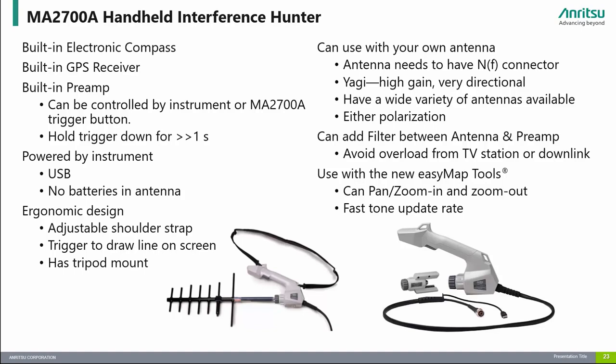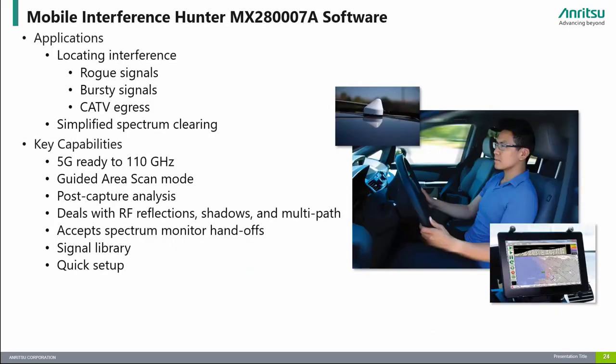The frequency range of the MA2700A is from 10 MHz to 6 GHz. Anritsu's mobile interference hunter MX280007A works with a broad array of Anritsu's handheld spectrum analyzers, providing interference hunting and spectrum clearing capability from 9 kHz to 54 GHz. The system uses proprietary interference-finding algorithms that quickly determine the position estimate of an interfering signal. Once sufficient measurements are accumulated in area scan mode, the software can create a heat map indicating the position of the interference source, with the signal location estimate continually refined as more measurements are taken.